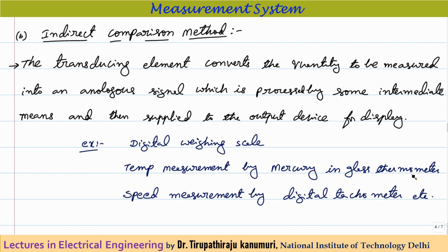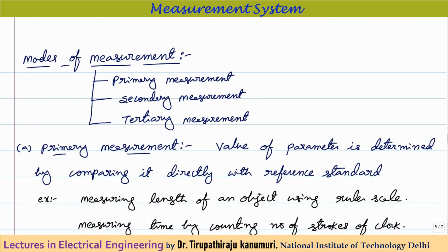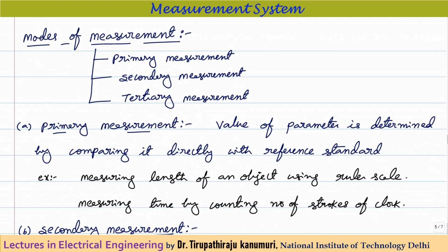Another example of indirect measurement is temperature measurement using a mercury-in-glass thermometer: the temperature is converted into expansion of mercury, which you then read. Similarly, speed measurement using a digital tachometer is indirect — the rotating shaft drives a small DC generator, and the voltage generated depends on the rotor speed. That voltage is measured by a voltmeter whose scale is calibrated to indicate rotor speed.